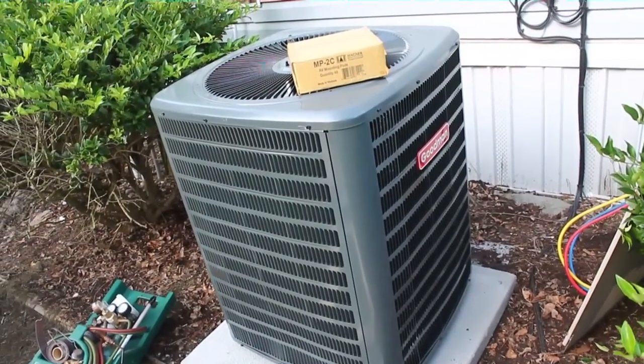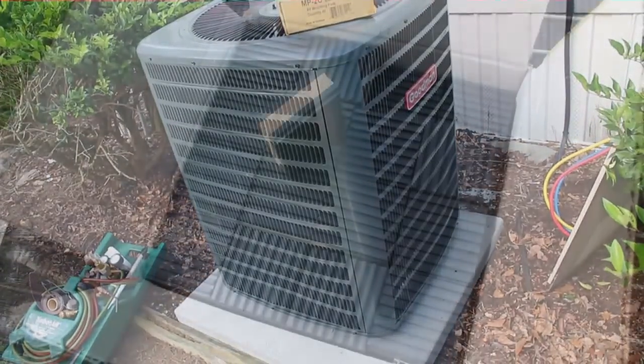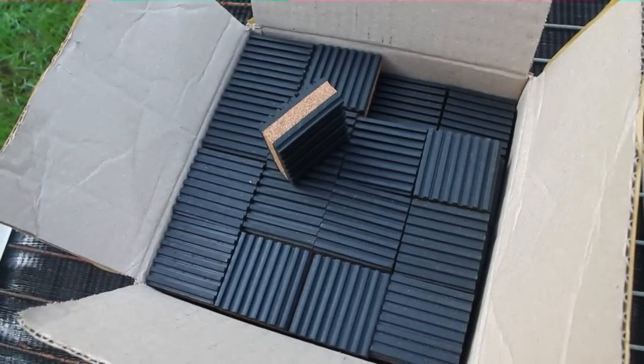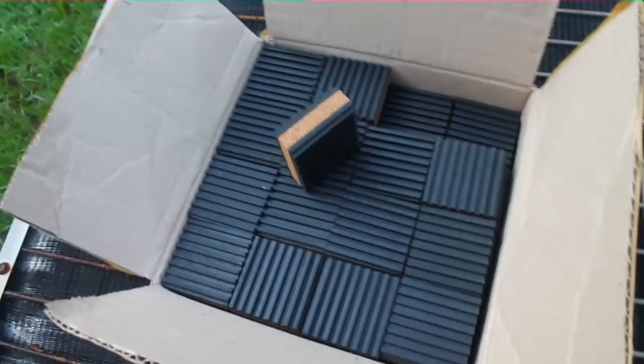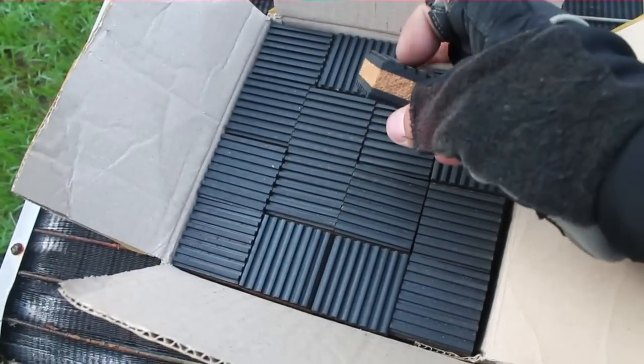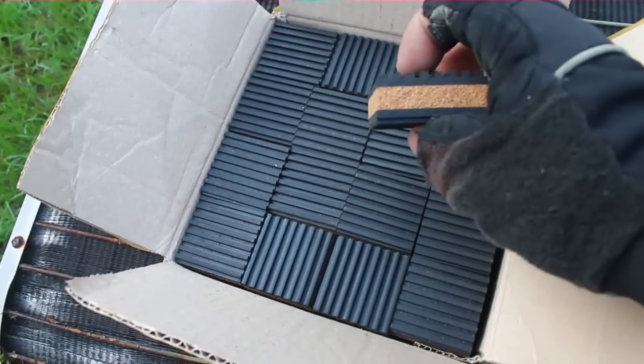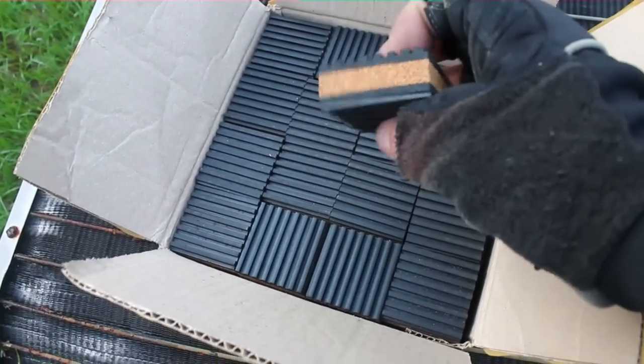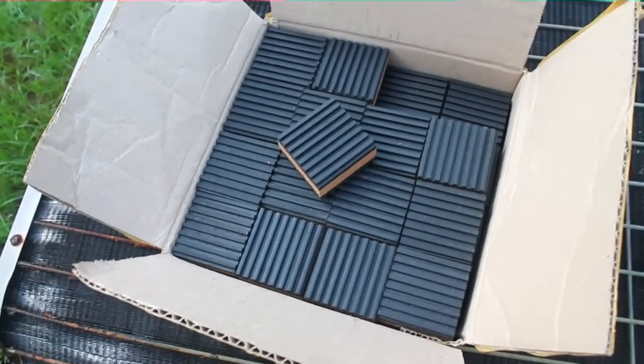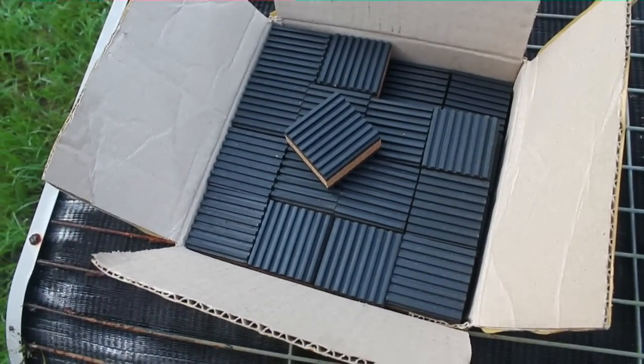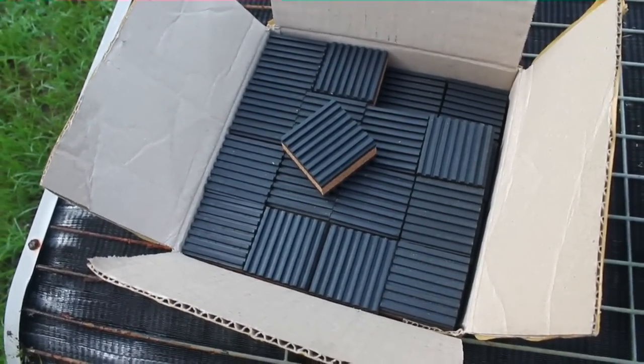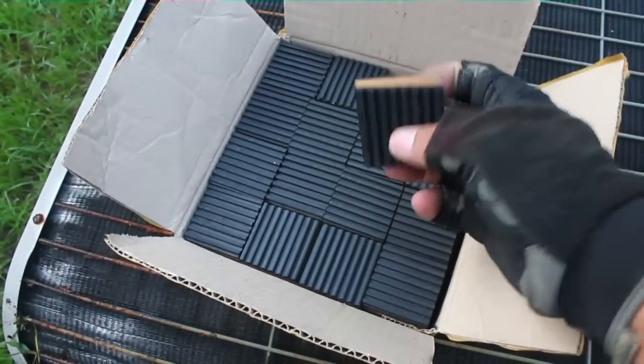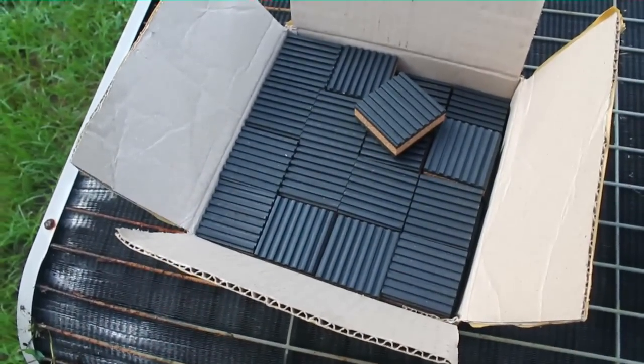I'm going to level it up. Then I'm going to move on with the installing process. I like to use these sort of vibration pads underneath the outdoor unit sometimes, because you can actually separate the rubber part from the cork part. So if you want like a 3/4 to 1 inch rise, you can put a whole pad underneath it, or you can rip the little pieces apart just to get like a 1/4 inch rise out of it to level things up. They work pretty good. Usually buy them in bulk, 48, but they come in real handy.